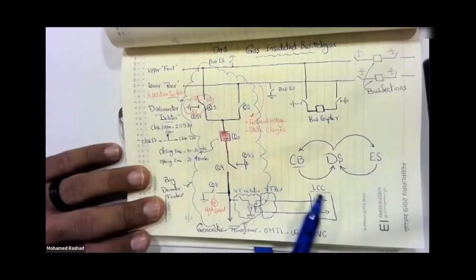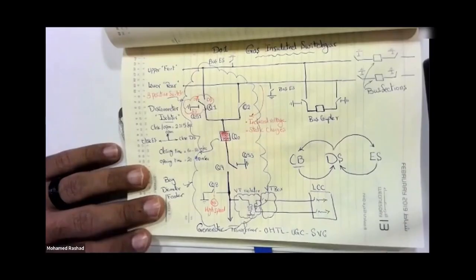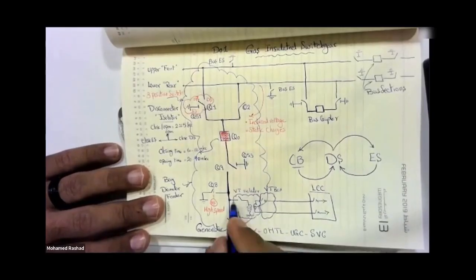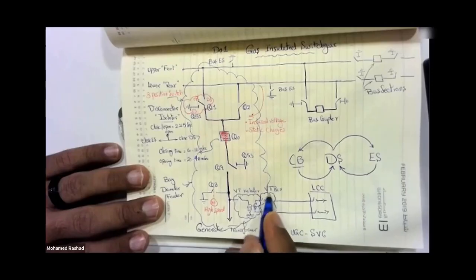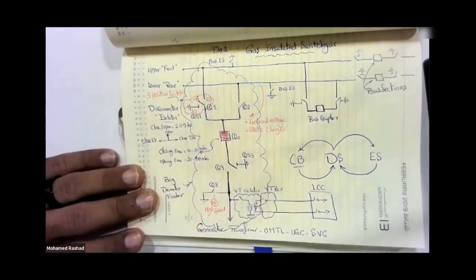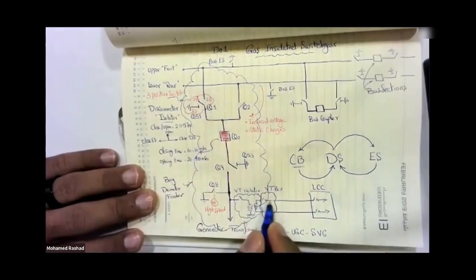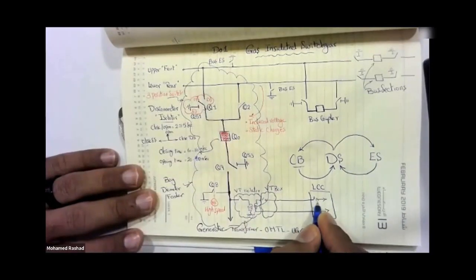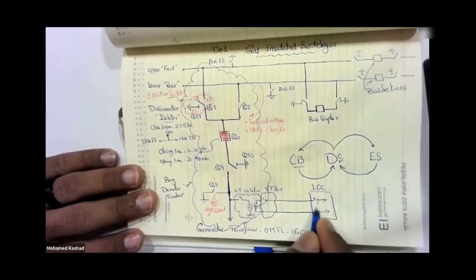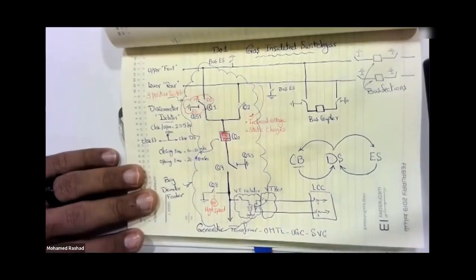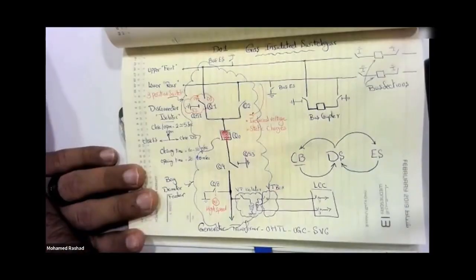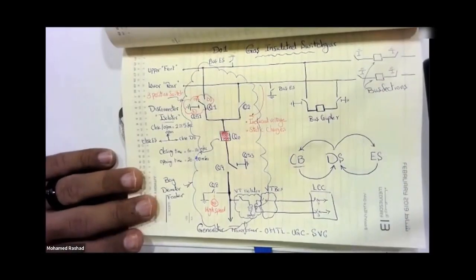Consequently, the voltage that reaches your PCU or your synchroscope in both cases will appear dead. Alternatively, you might have closed the isolator, but left the VT MCB open, which is located in the VT box at the GIS itself. Well, you might have closed it as well, but then you have to consider who is supplying the voltage to your system. That source might also be disconnected. Right? Isn't that the case?